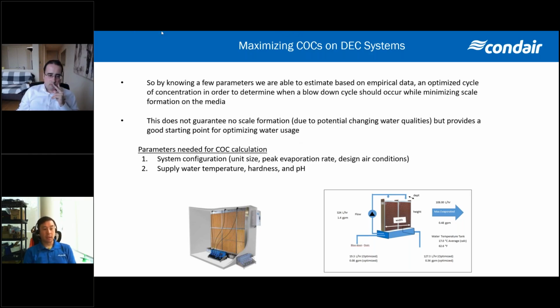So when we look at this, really all we need to know to do this calculation is the system configuration. So that's going to be your unit size, the peak evaporation rate, which is typically what we use to design the performance of the system around, and then the design air conditions. And then on the water quality side, what we would typically be asking for is the supply water temperature, the hardness, and the pH going into the system. Just to give you an idea there, pH range, we typically try and keep between 6 and 8. Ideally, the closer to 6 we are, the better we are in terms of running a higher COC or higher water efficiency at that point.